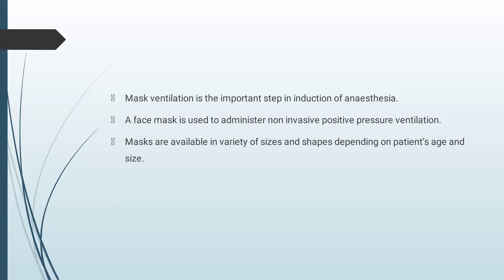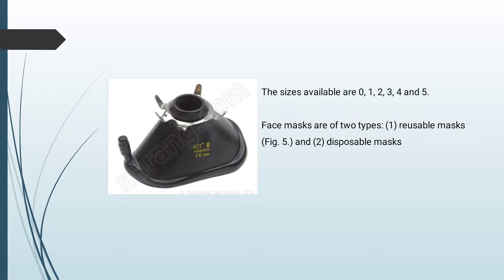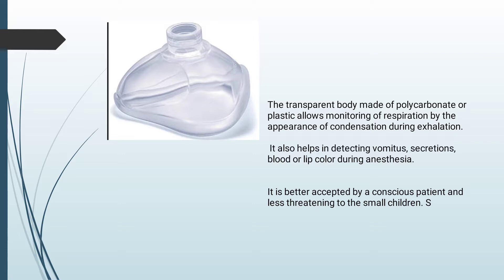Mask ventilation is the first important step in induction of anesthesia. A face mask is used to administer non-invasive positive pressure ventilation. Masks are available in a variety of sizes and shapes depending on patient's age and size. The sizes available are 0 through 5. Face masks are of two types: reusable masks and disposable masks. The transparent body made up of polycarbonate or plastic allows monitoring of respiration by appearance of condensation during exhalation. It also helps in detecting vomitus, secretions, blood, or lip color during anesthesia.